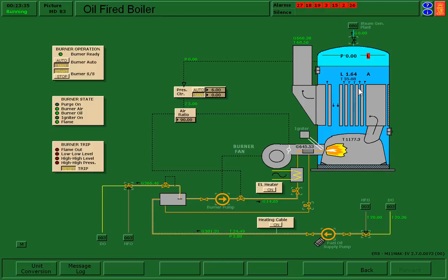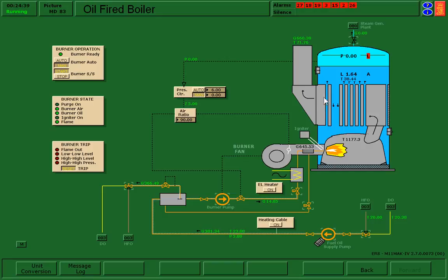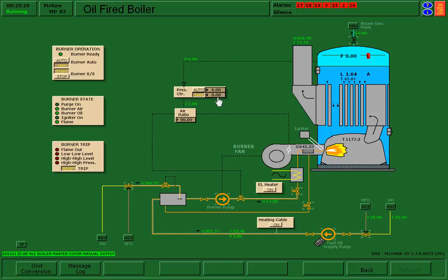I want to keep the flame at a fairly low heat output during the startup. What we don't want to do is thermally stress any of the components by heating them up quicker than any neighboring components. So I want to warm this thing up slowly as one large component as evenly as I can. We're going to keep our heat output or our burner output, which is this value, down at a minimum fire level or close to it for the startup.